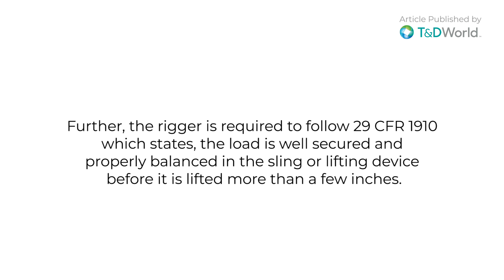Although the use of FIBCs to lift transformers or other electrical equipment is somewhat isolated, it is happening in the industry. These unscrupulous companies are claiming that FIBCs can be used to lift transformers, as described above, and claim OSHA and UNDOT compliance with tremendous weight capacities. Weight capacities that are calculated using ISO 21898 standards that are for FIBCs filled with flowable materials, with even distribution of stresses across all surfaces of the FIBC. Not point loading caused by placing an article, like a transformer, inside an FIBC.